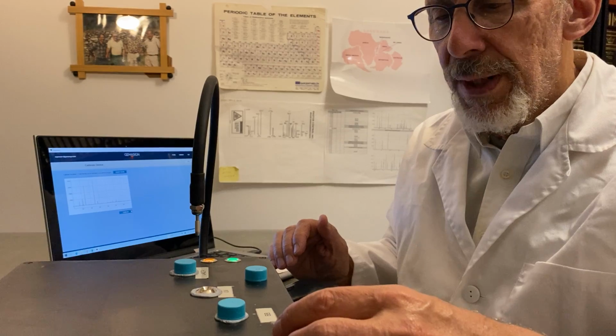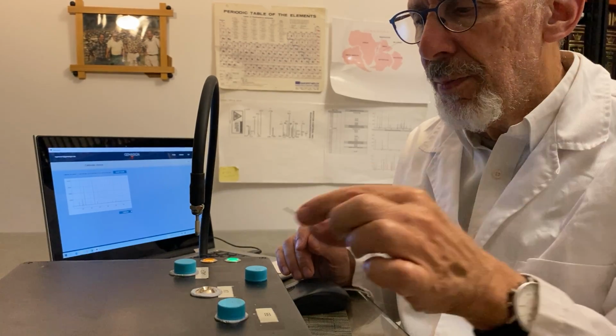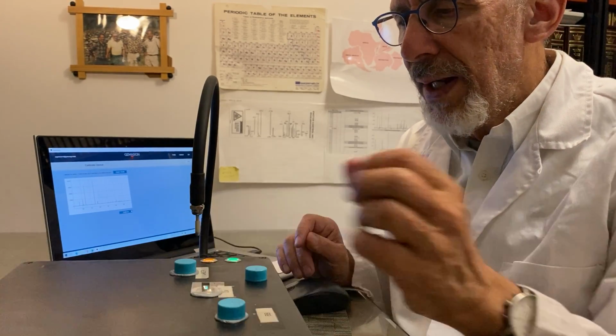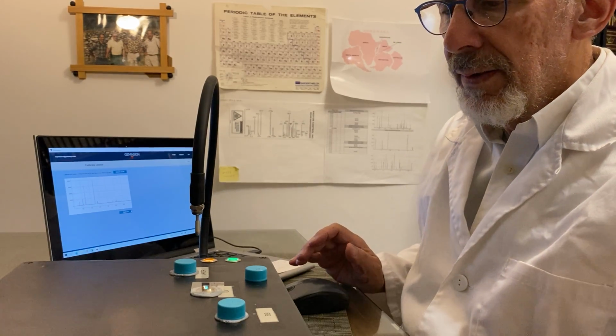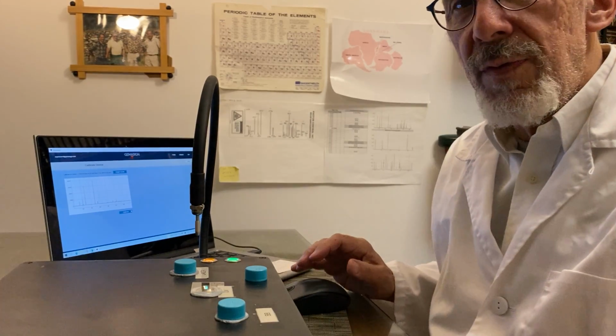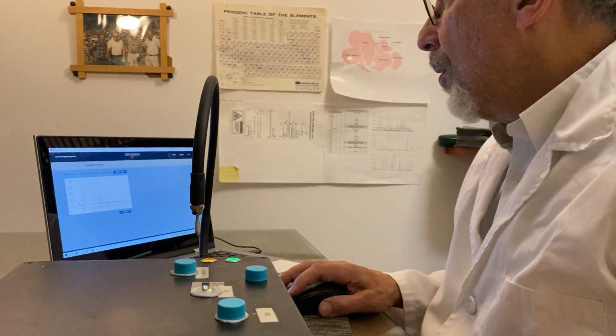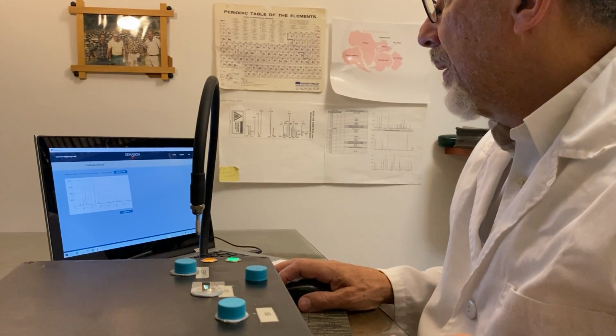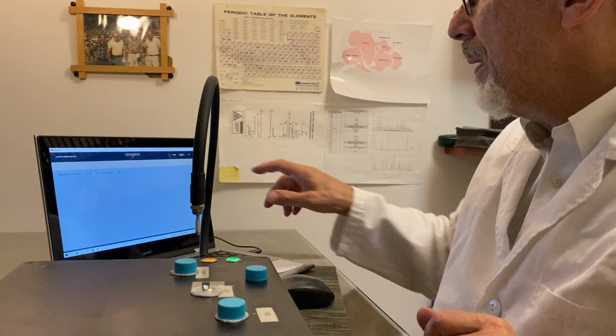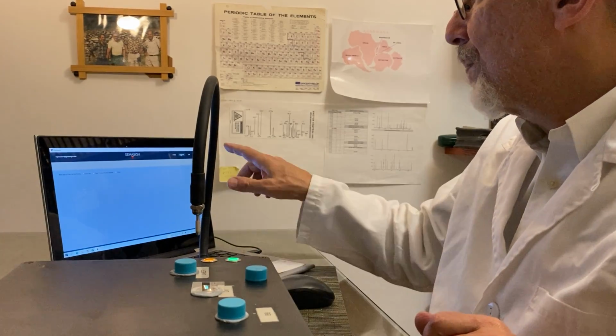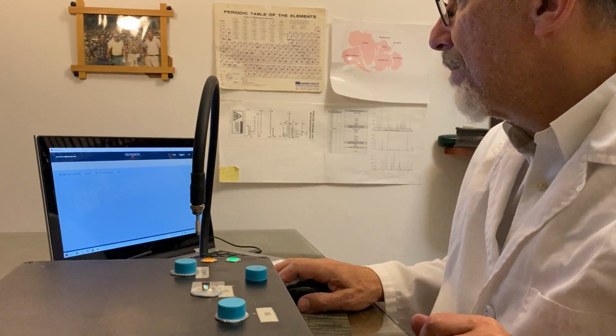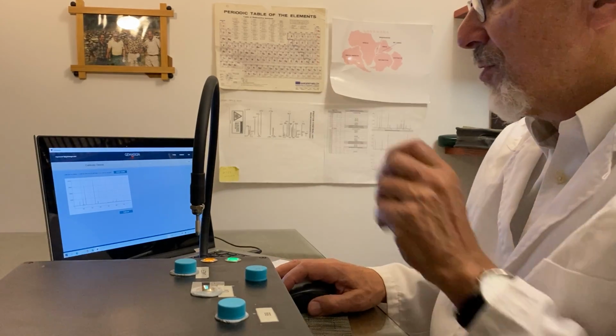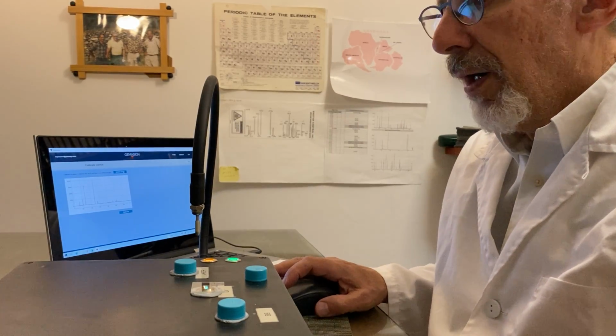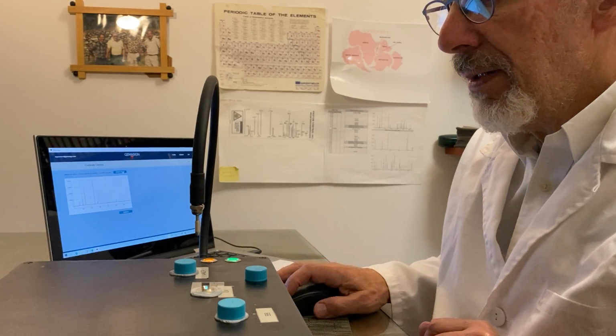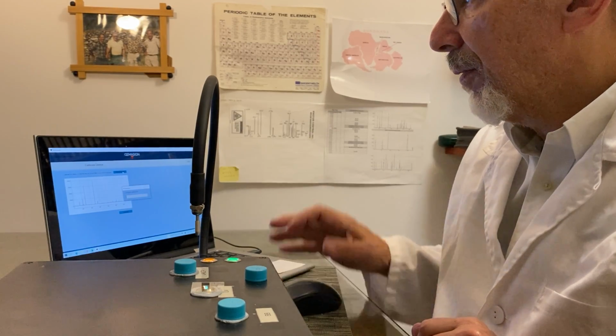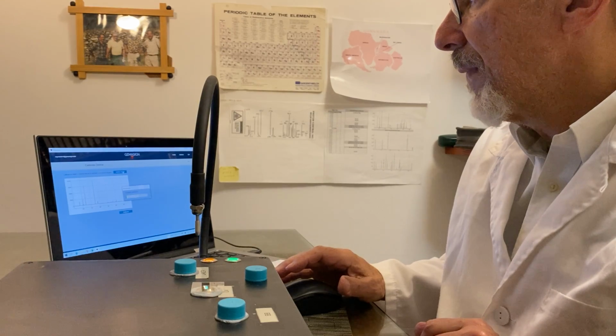In order to do the calibration, we use a standard microscope slide and we paste that over the port for the UV. Going into the program, I can come out of the program for a second. Okay, if you go in, I'll show this enlarged, but there is a button called Calibrate. You click on that and the spectra opens up. All you have to do is press Start Scan and it'll take a UV spectra.